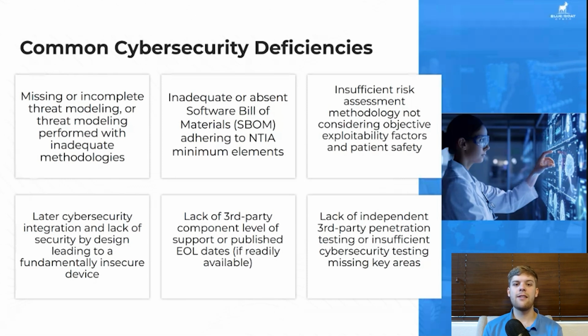Something else that we see are insufficient risk assessment methodologies. The FDA wants to see objective exploitability factors and consider patient safety when we're looking at the impact. We'll take a look at what that looks like in practice here in a minute, but it's very common for manufacturers to use a probabilistic assessment methodology using words such as probability or likelihood, which are going to be subjective. I may have a different opinion than another assessor, and that is not acceptable. The FDA wants to see that multiple assessors are going to come to the same conclusion based on the same information.